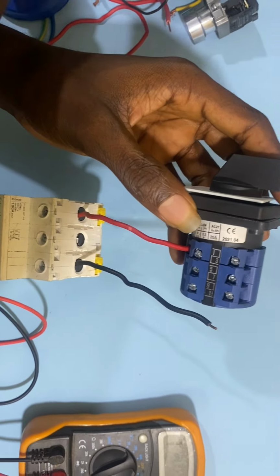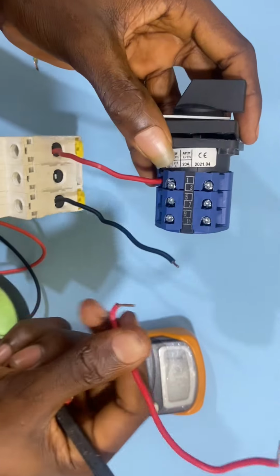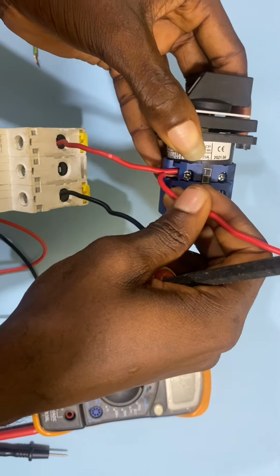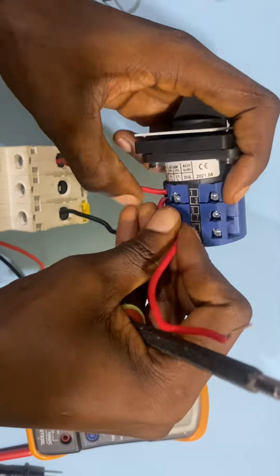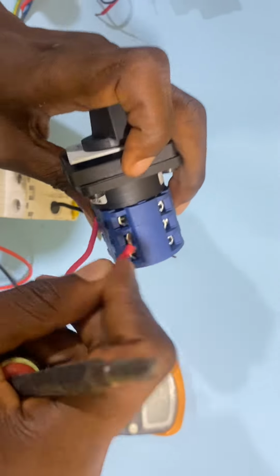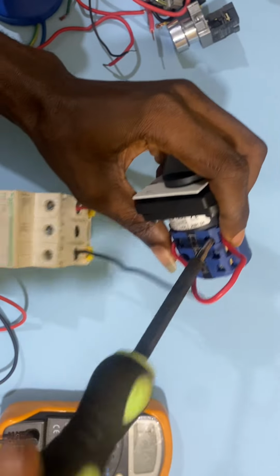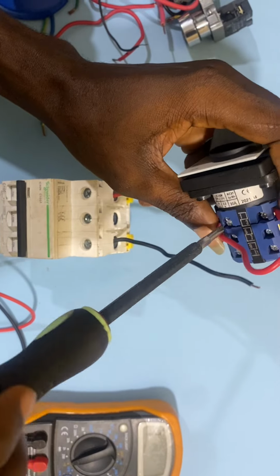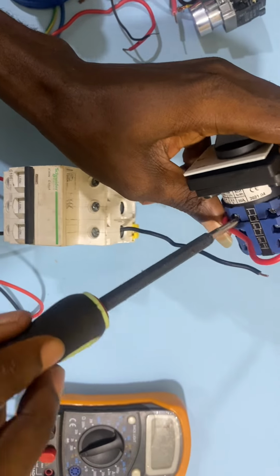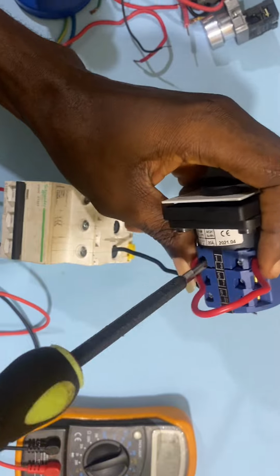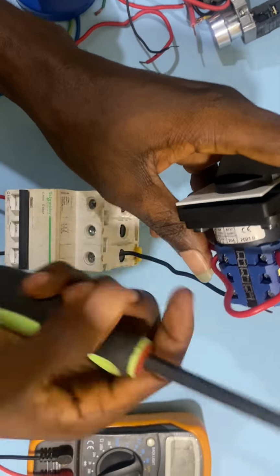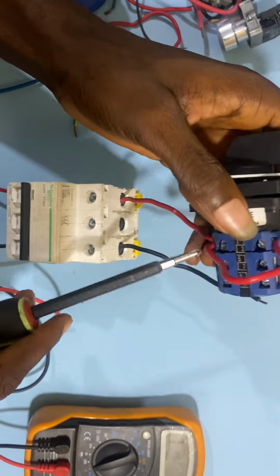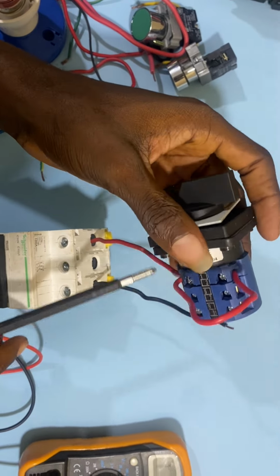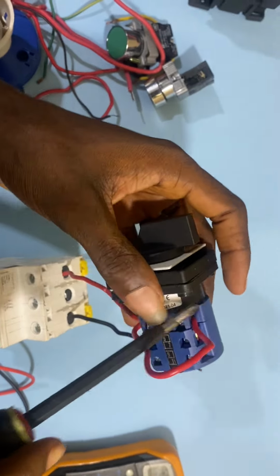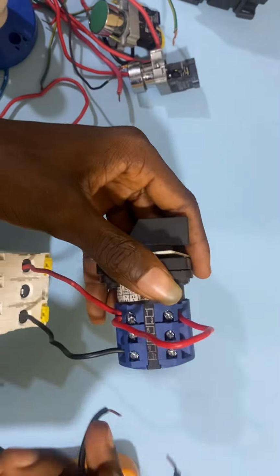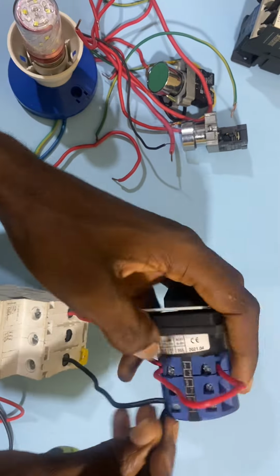So I'm going to bring my jumper. So this is my jumper. I'm going to loop from this position down to this position. To do this, I screw it down, screw it down. This simply means that I've successfully looped a live main input from this phase to this other phase. So I will do the same to the neutral side. So how do we do the looping? I'm going to loop from here to here.